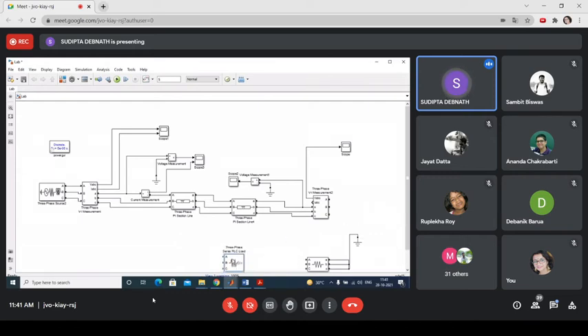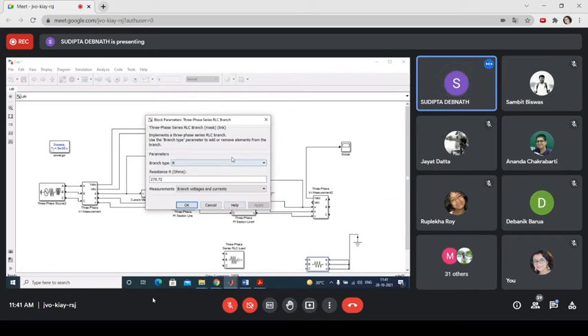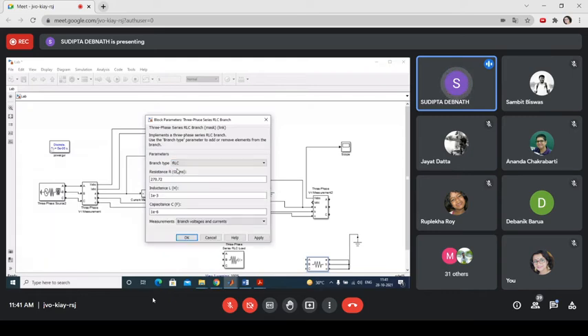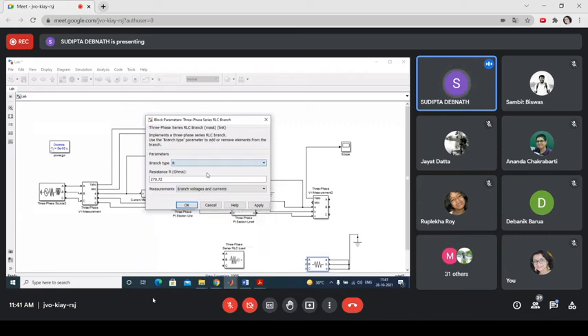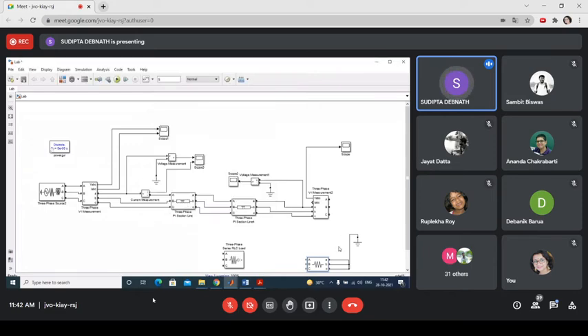The difference between this block and this block is that this one will show the load P, Q etc, and this one will show the resistance. If we want to give the inductance, you have to put RLC, it will show R, L and C. But we need to connect only the resistance, so put it as R, resistive load, it is a 3-phase resistive load. What value do we put? 270.72, because this is the surge impedance, the characteristic impedance of the line. So let us connect it here.